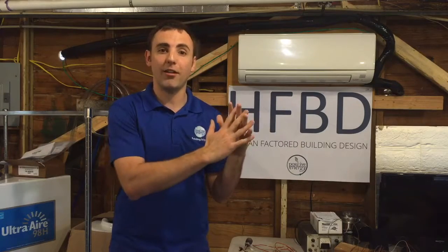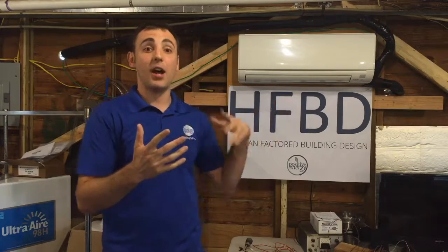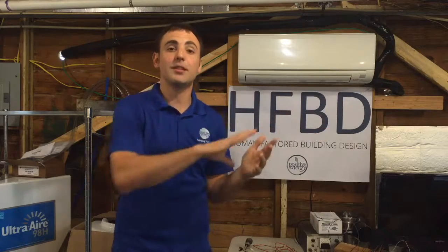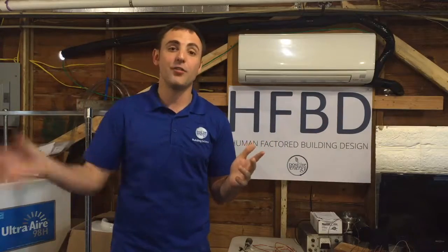When you have return side duct leakage, you're going to be introducing 90 degree air, maybe it's air from your attic, 100 degree air that also hasn't been dehumidified yet, which means that you're introducing hot, humid air into this cooler air environment. Now that those airs start mixing together, you now have a warmer temperature on your supply side than you ideally would, which means it's going to take a lot more circulation of that warmer air in order for you to be comfortable in that room.